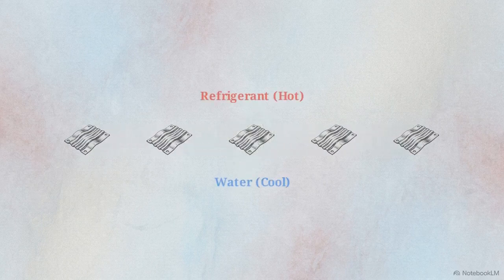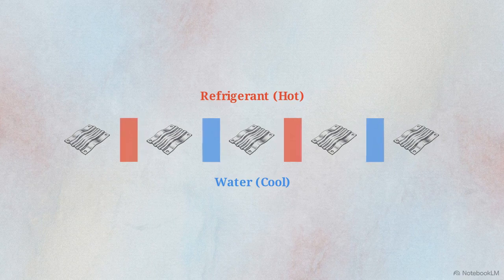This exploded view illustrates alternating channels where refrigerant and water flow closely past each other, separated only by thin, corrugated stainless steel plates. The corrugated geometry forces the fluids into a turbulent flow, churning the liquids to maximize heat exchange in a fraction of the space required by a traditional shell and tube design.